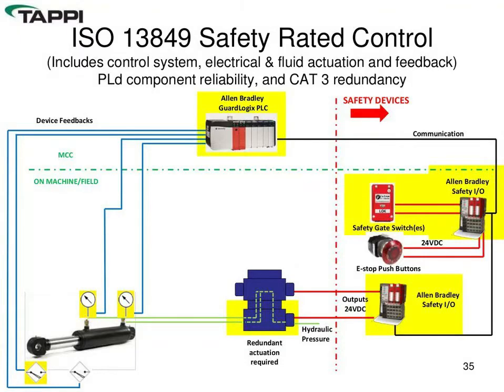And this is the new circuit compared to the circuit I showed before that we would have on a PLC rated circuit. So we'll generally have a safety PLC, dual contacts from safety devices, redundant actuators for movements. In this case we're showing two solenoids that need to turn on to cause movement. The device will have extra monitoring to tell if it is really moving or pressurized. And this is a typical circuit.